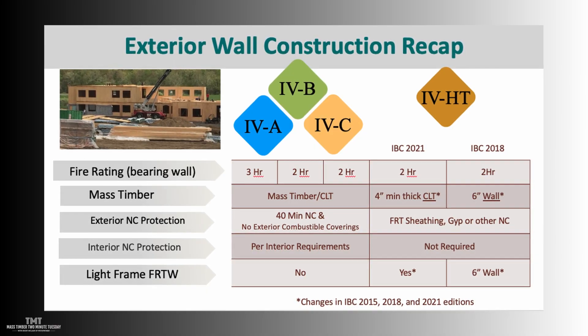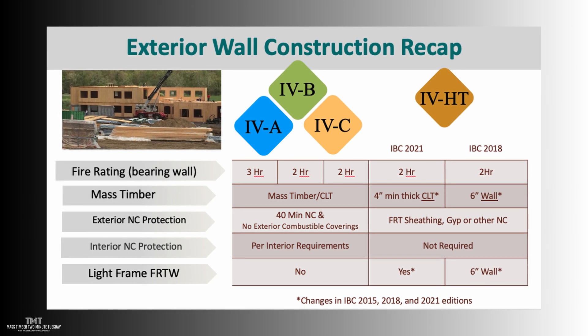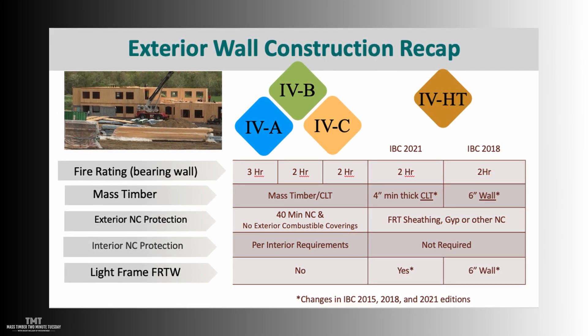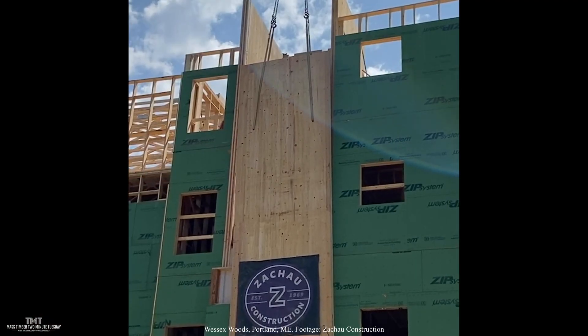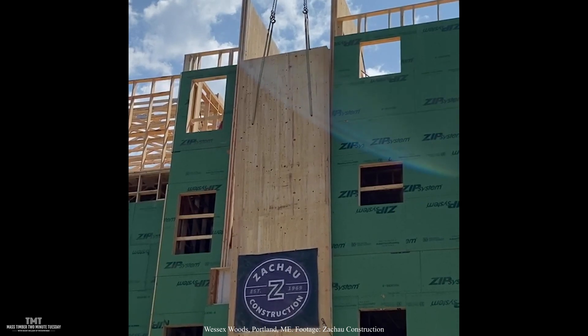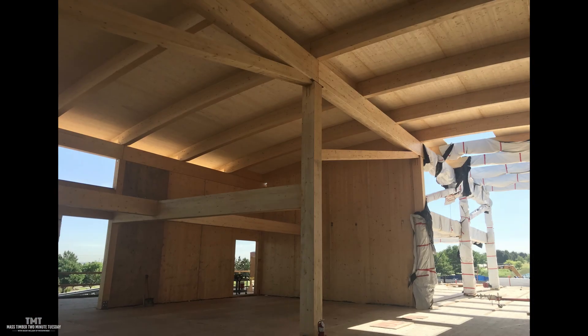In the case of Type 4C, 4B, or 4A, we're now having to demonstrate that the layer on the outside face of the mass timber exterior wall panel has a minimum 40-minute fire resistance rating. In 4A and in some cases 4B, if we're using mass timber as the exterior wall panel there is also a requirement for encapsulating the interior face of those exterior wall panels. If we're using mass timber in the exterior wall of a Type 5 construction building, the code does not have any prescriptive requirements for timber encapsulation, though it is possible that the exterior wall has a fire resistance rating requirement.